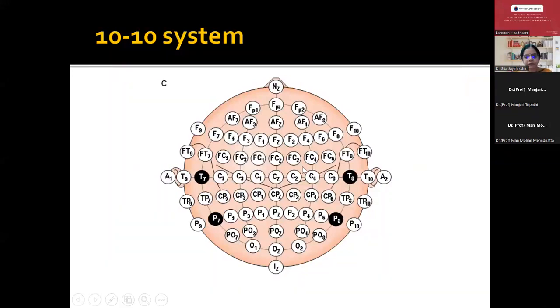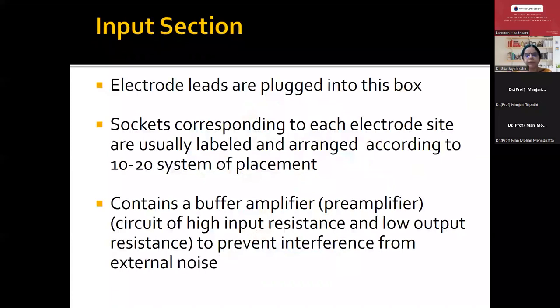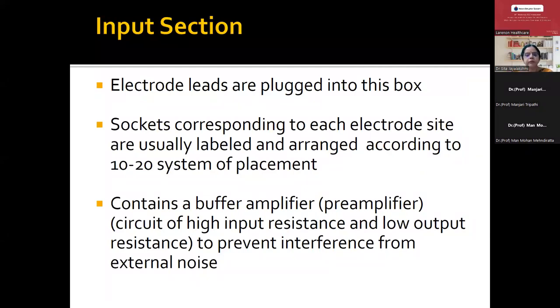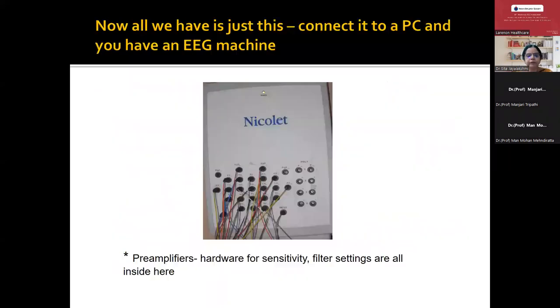There is also a 10-10 system, which most of the time we do not use, where all the electrodes are placed at 10% instead of the initial 10% followed by 20%. Once the electrodes are placed on the skull, we should know about the input section of the head box. The electrodes are plugged into the input section, sockets corresponding to each electrode site are labeled, and the socket contains numbers — so F3 will go into F3, PZ into PZ. It contains a buffer amplifier or pre-amplifier to prevent interference from external noise.